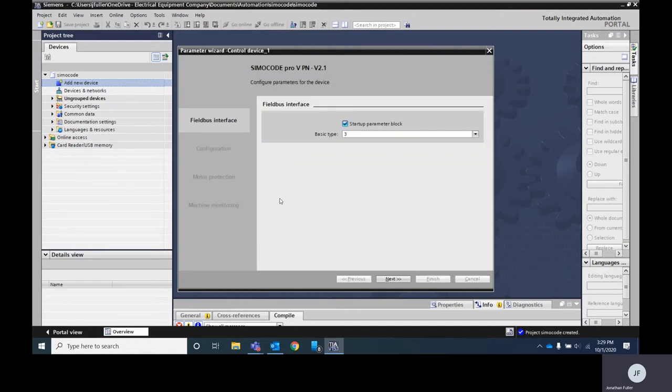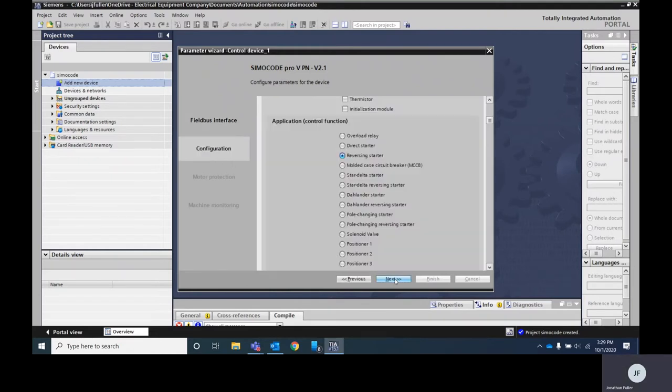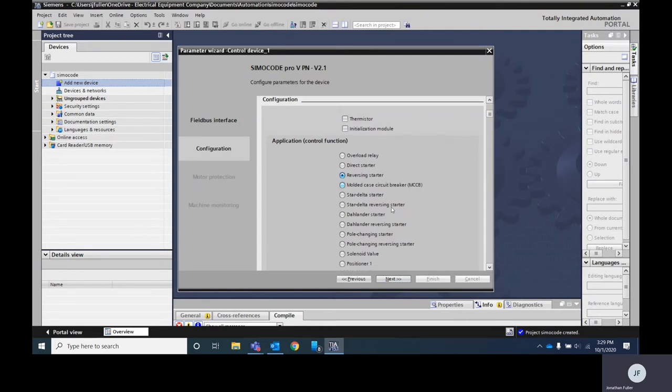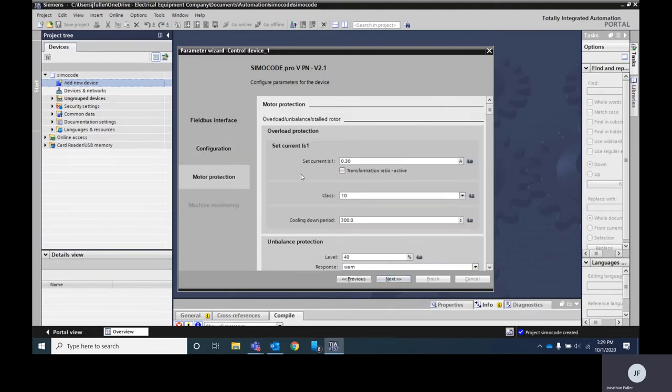Once we've hit finish our parameter wizard is going to pop up and it's going to ask us a couple of different questions. In this screen we're going to be able to set the different types of application and it should carry over from the previous selection. Just to make sure we're going to make sure we have reversing starter selected, we'll hit next.